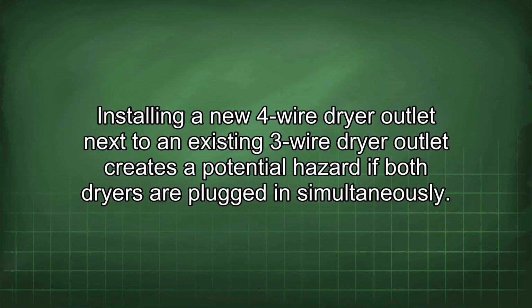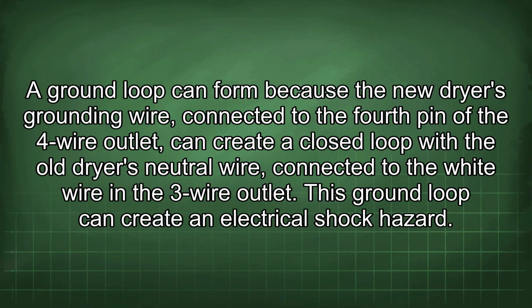Installing a new 4-wire dryer outlet next to an existing 3-wire dryer outlet creates a potential hazard if both dryers are plugged in simultaneously. A ground loop can form because the new dryer's grounding wire, connected to the 4th pin of the 4-wire outlet, can create a closed loop with the old dryer's neutral wire, connected to the white wire in the 3-wire outlet. This ground loop can create an electrical shock hazard.